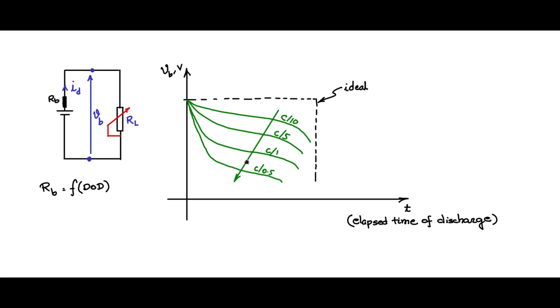You will see this family of curves where the arrow indicates increasing discharge current ID. It is very important to note that C-rate plays a very important role in selecting a battery — if you want a specific discharge time on the x-axis and want the terminal voltage to remain within a particular limit, you must choose an appropriate C-rate and also the appropriate depth of discharge. These are important parameters to consider while selecting a battery for a given application.